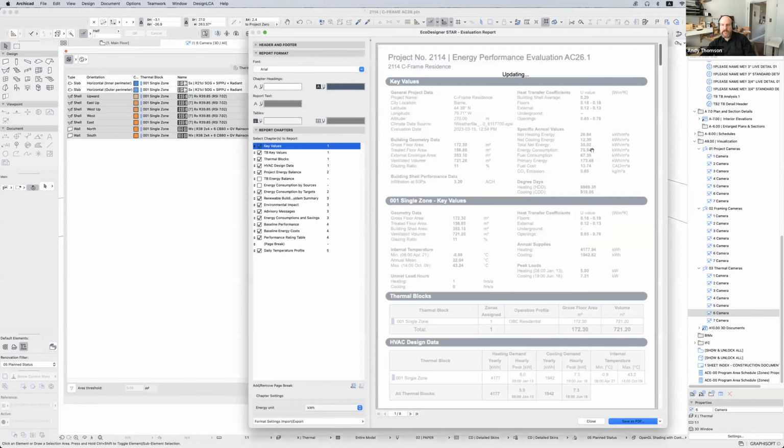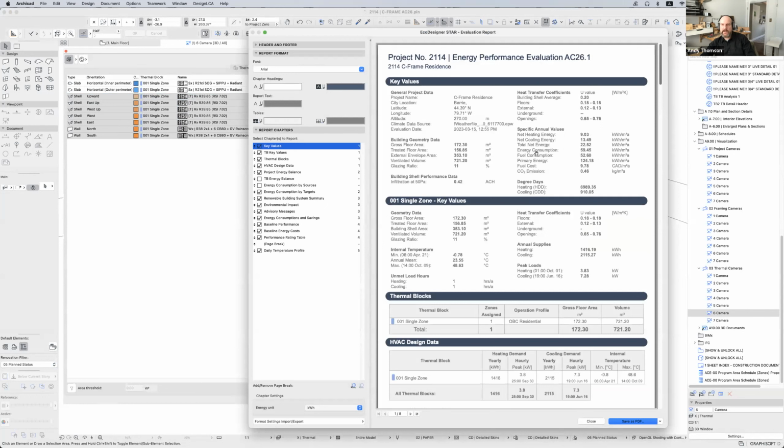And we're down to 0.42 now, and our EUI has gone down to 59. So it's a pretty easy way to have a pretty massive impact on building energy modeling. Depending on what standard or what level of building code you're targeting, you can adjust the airtightness of the assemblies to give you the air changes per hour at 50 Pascal, that number. And you can progressively go through the model, making these little tweaks and changes until you get your EUI optimized.